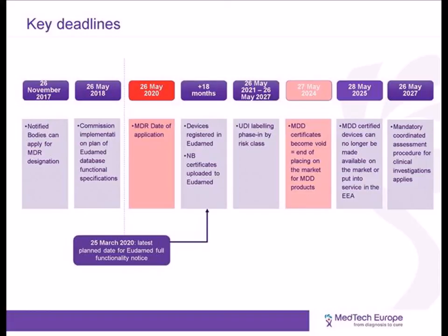Notified body certificates issued before May 2020 and under the previous directives will remain valid until the end of the period stated on the certificate, up to a latest of May 2024. 27th of May 2024 is the last possible date that devices certified to the previous directives may be placed on the market.